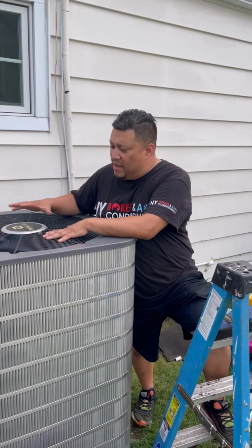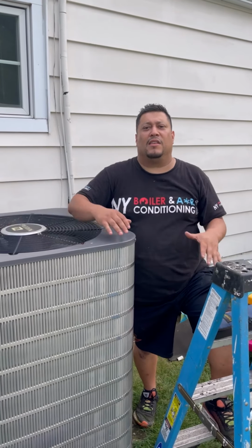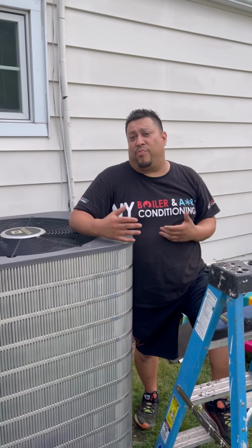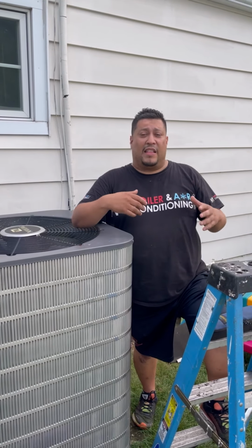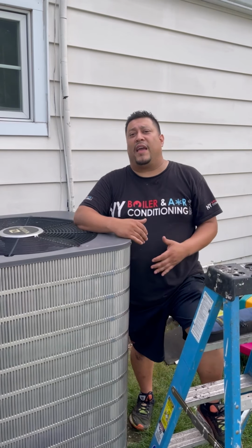Guys, we're here in Rockville Center, New York. We're actually working on a condenser unit. It's an old R22 system. It's an old Maytag unit. So we get the call and the guy tells us, listen, the breaker's shutting off. So meaning that the indoor unit is turning on, but every time he turns on the breaker, it pops. Sure enough, I get here, the condenser is off.